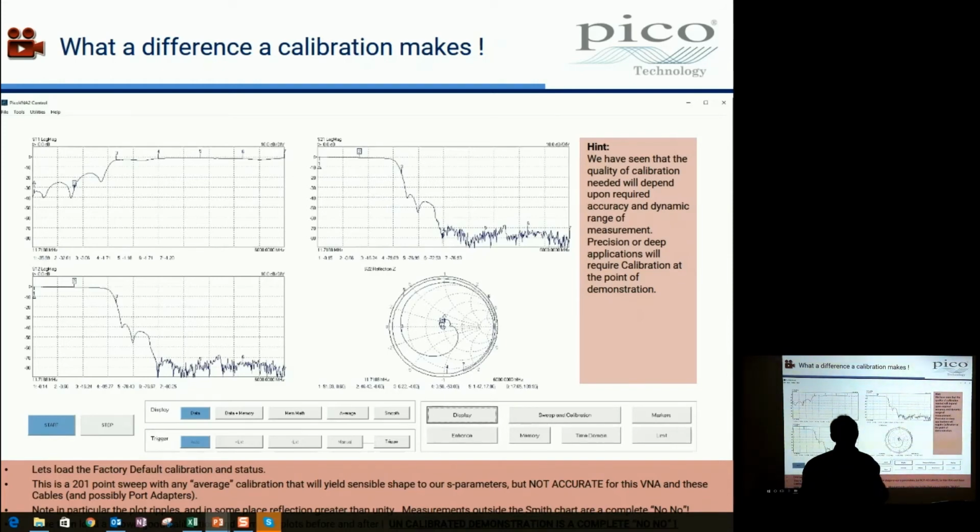So always use either the demo cal, or one that you've prepared for yourselves, but don't do no cal at all, or leave the cal that was last used in front of whatever customer.